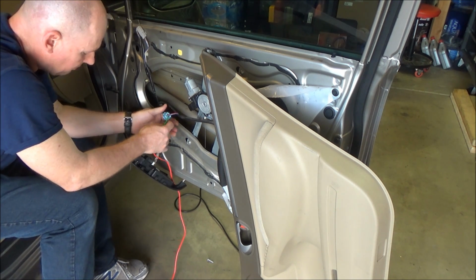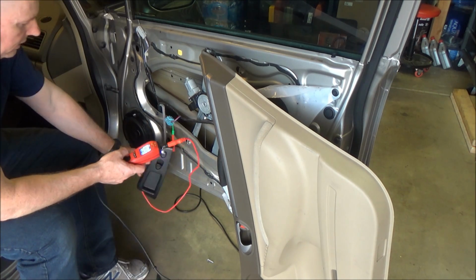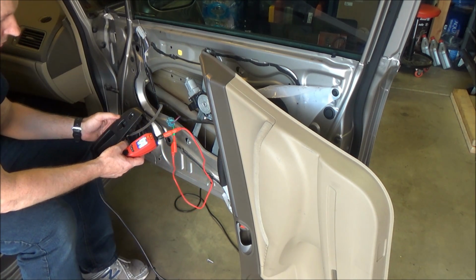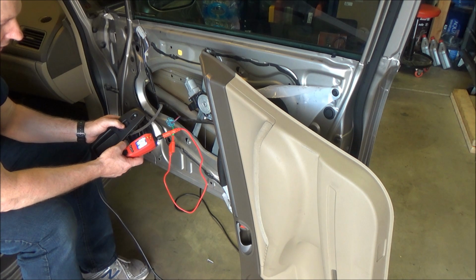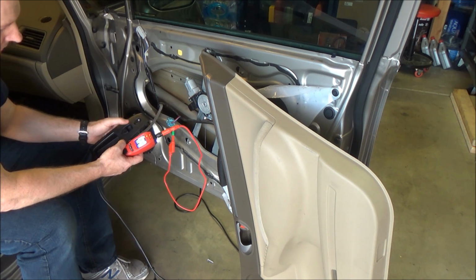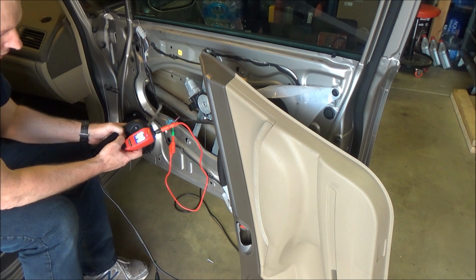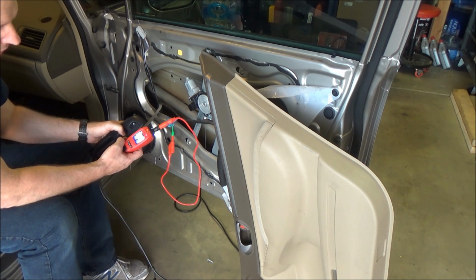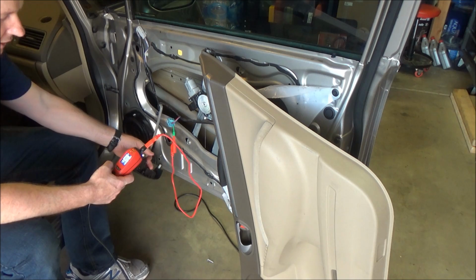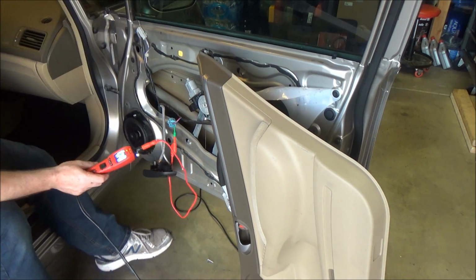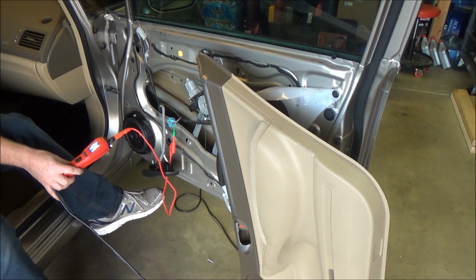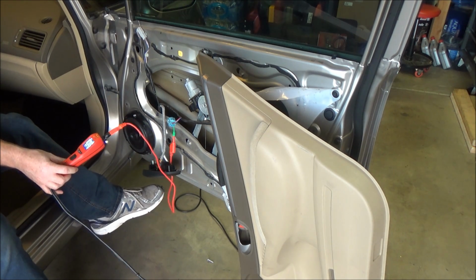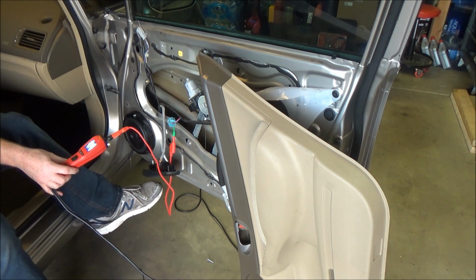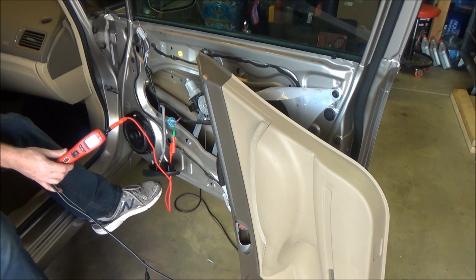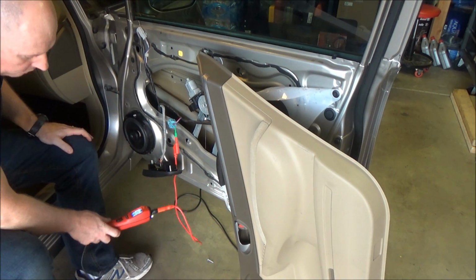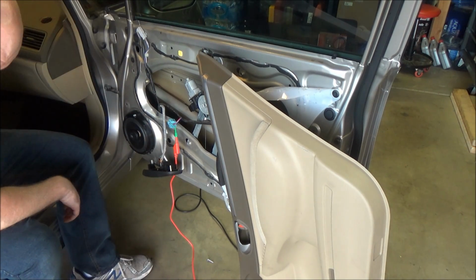Once we disconnected the motor, we disconnected the load, but you can see once again it's 0.02, press it down, stays on 0.02, press it up, goes to 12.01. So it looks like our switches, everything is working properly. Actually, let me test the other one. Down, stays on ground, 0.02, and up, 12. Looks to me like our switches and everything, power, everything is working properly.